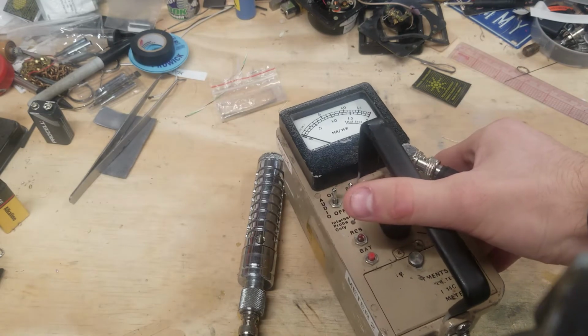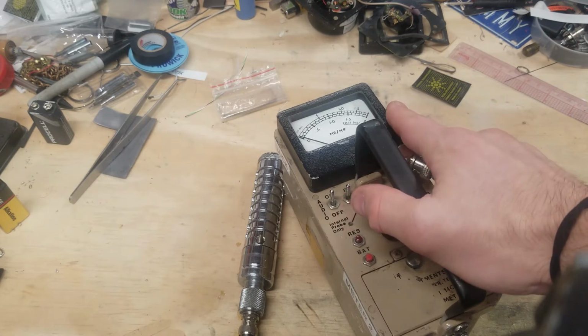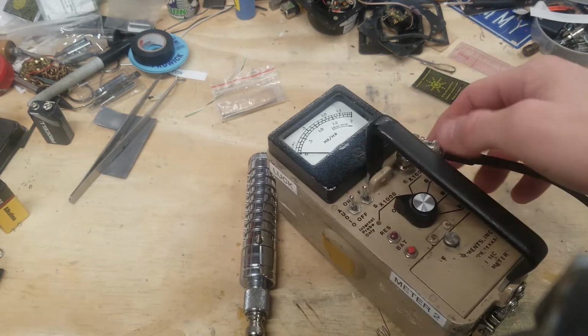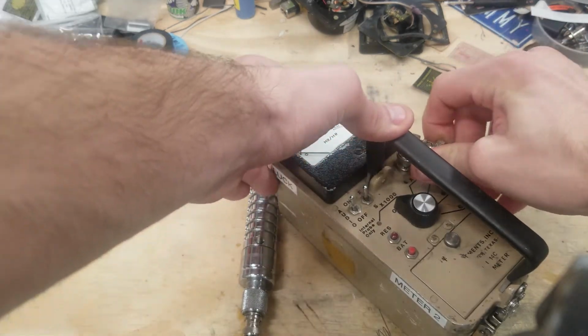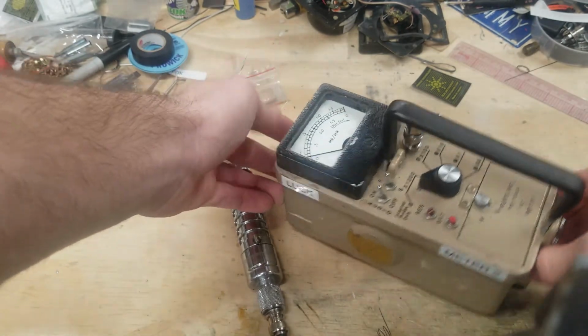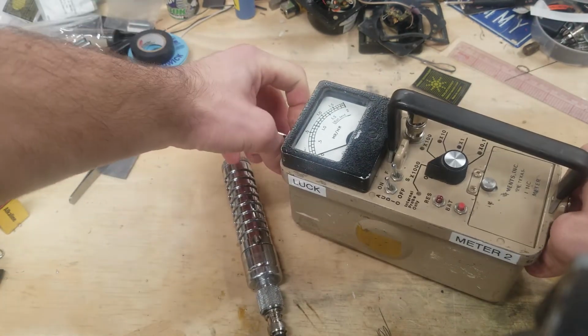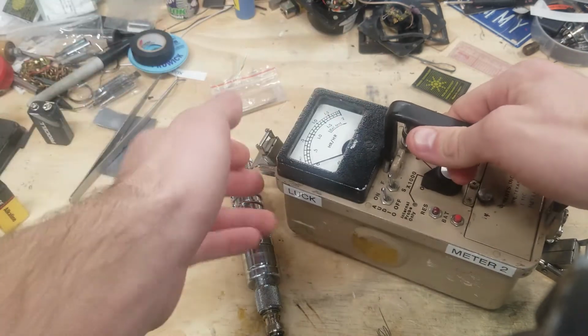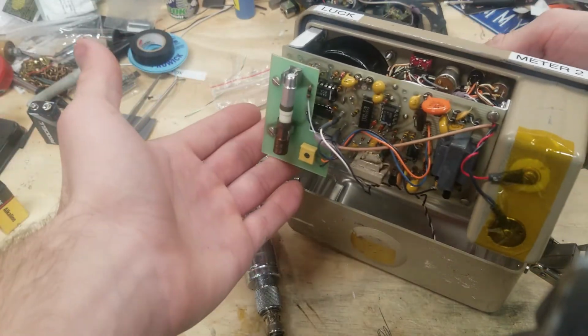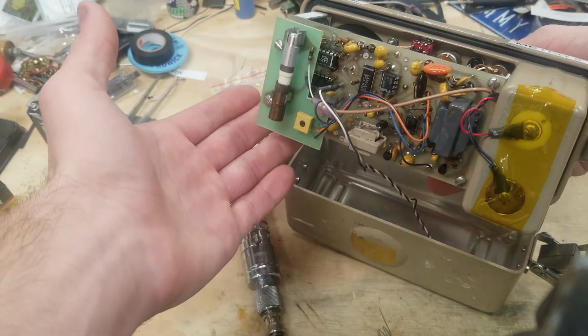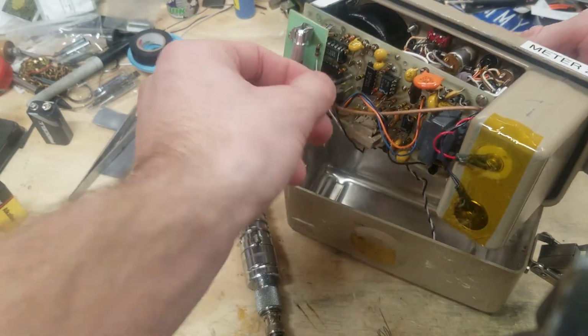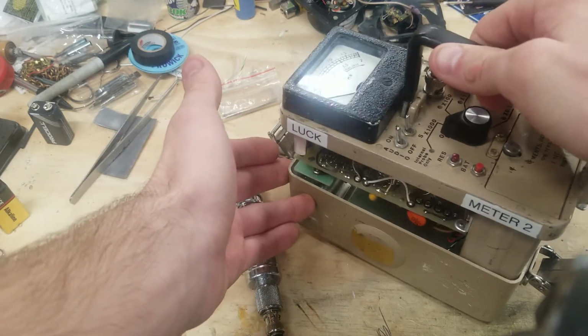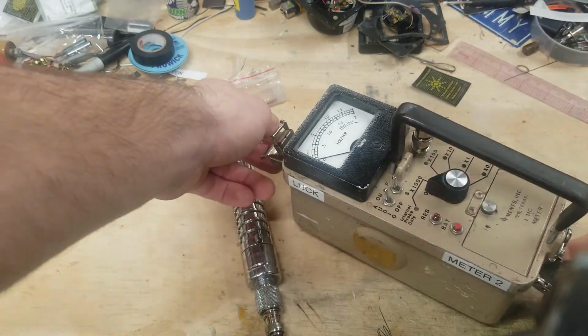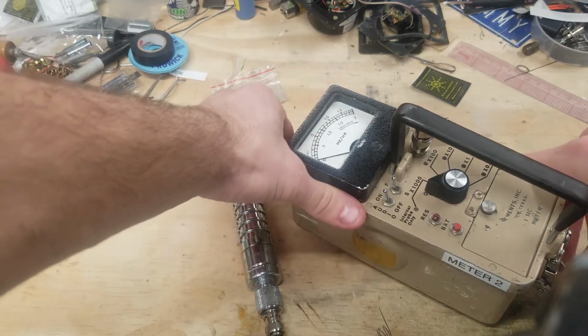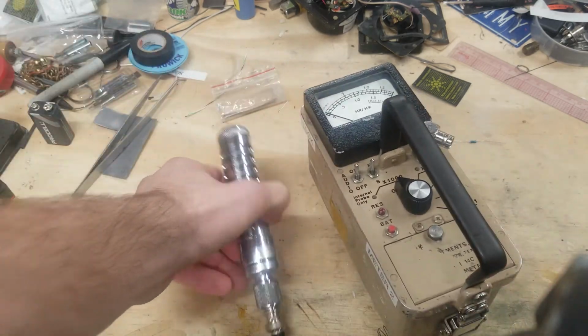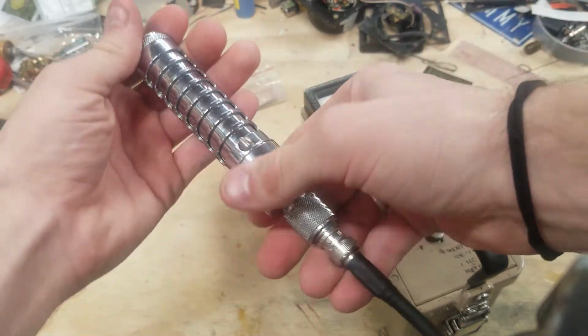These meters have one flaw, which is that the voltage is set to 900 volts specifically. This is done because it would be hard in an analog meter to change the voltage to allow both an external tube and an internal Geiger-Müller tube to be used in rapid succession. The internal tube is gamma only, with most external tubes, such as this pickle, being able to detect gamma plus beta.